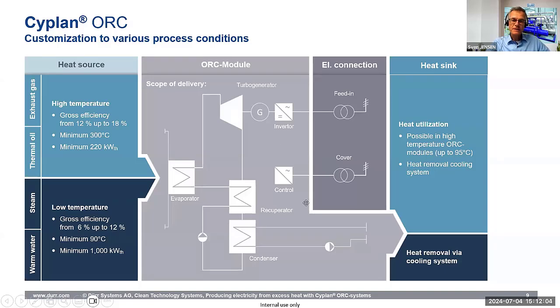I mentioned we have different ORC working media, but there's one major difference. If we receive the incoming heat at a lower temperature, then it's necessary to get rid of the heat at as low a temperature as possible. In practical terms, this means that behind the condenser there is a cooling tower, or a type of dry cooler—basically horizontal laminar coolers with a fan—so you dissipate the heat into the air.